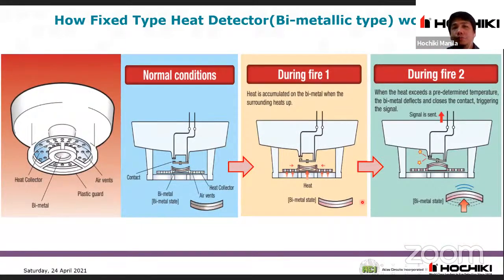Next is the fixed type heat detector, bimetallic type. How does it work? First, the parts of our bimetallic type heat detector: air vents, plastic guard, heat collector, and the bimetal. Inside, we have the contact here in this location, the bimetal plate here, then the air vents and heat collector. During fire, the heat collector detects the heat.